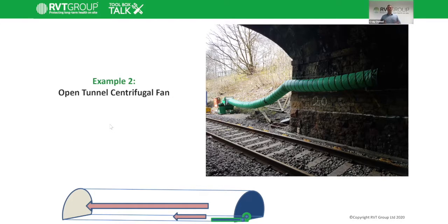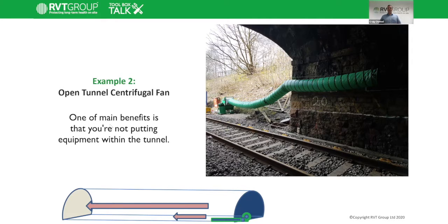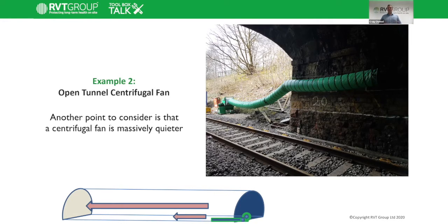One of the main benefits, one of the main features of this approach, is that you're not needing to put equipment within the tunnel. As you can imagine, this therefore has a major benefit in terms of not restricting the movement of plant that's already within the tunnel environment. Another important point to consider is that a centrifugal fan is massively quieter than the large axial fans. Particularly important if you're working in a sensitive, built-up environment, particularly if you're working overnight as well.